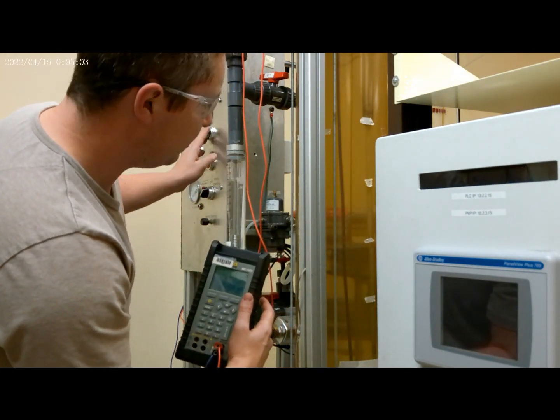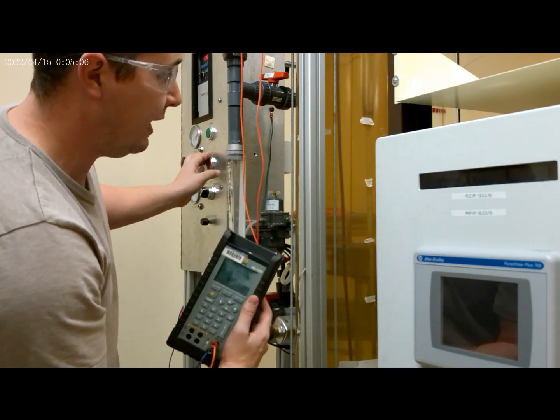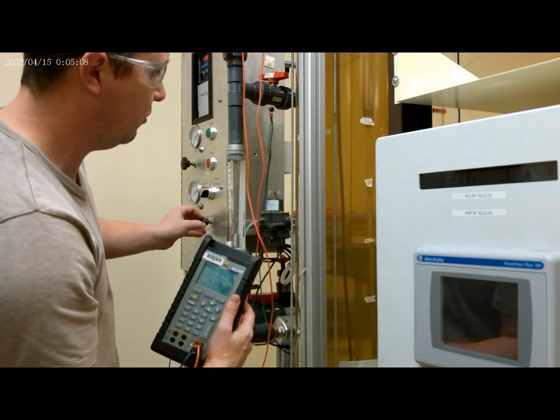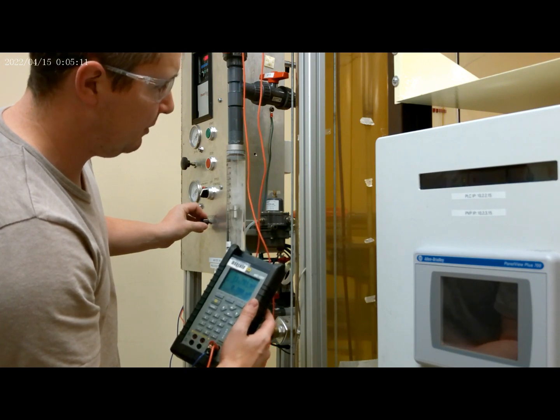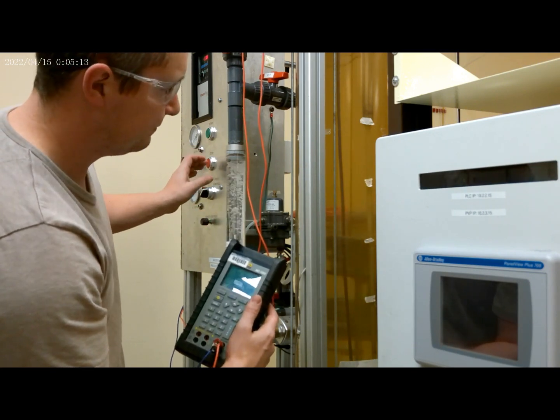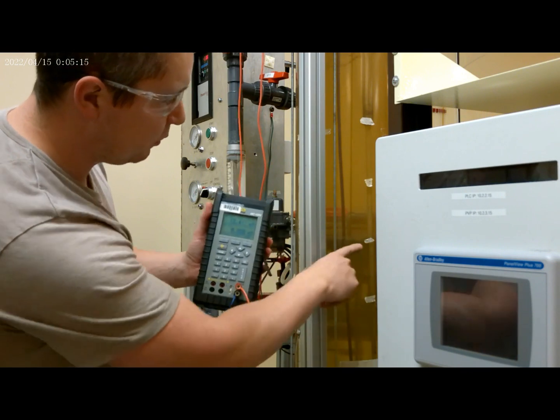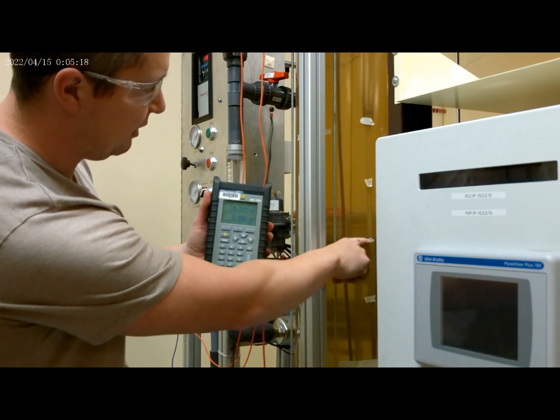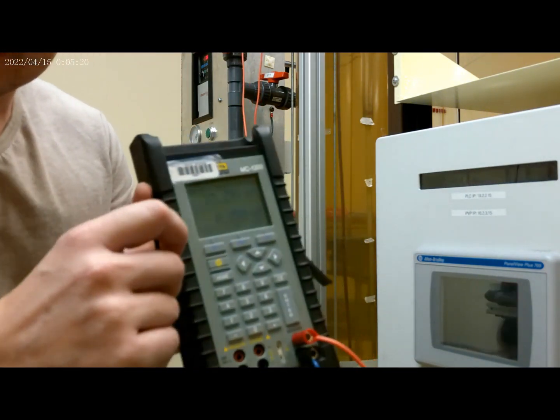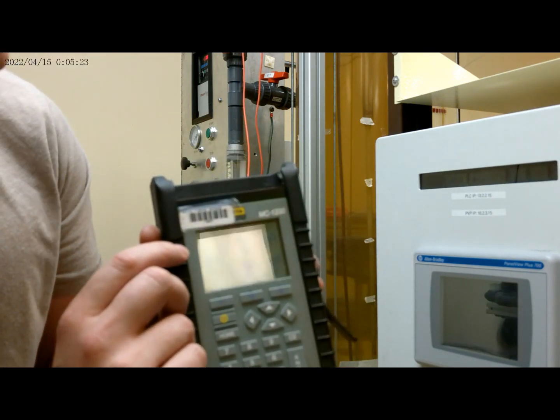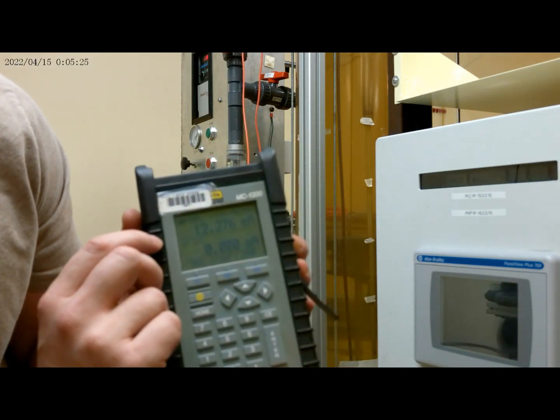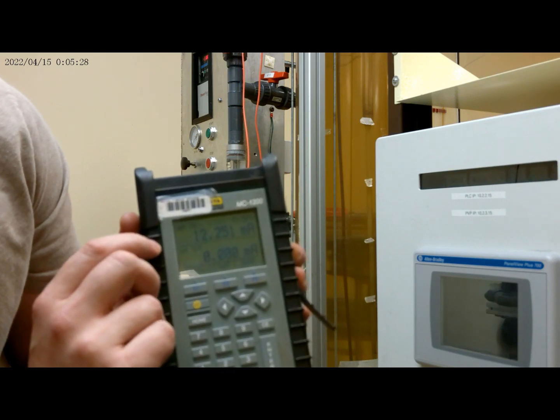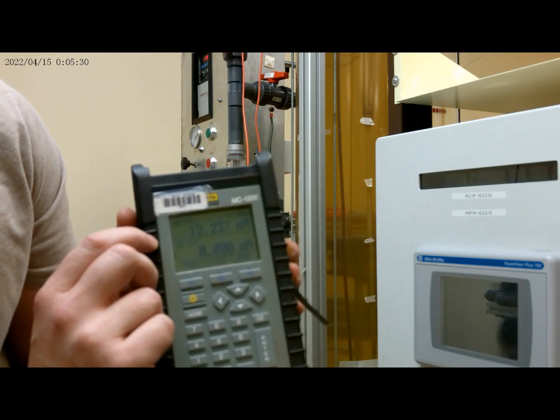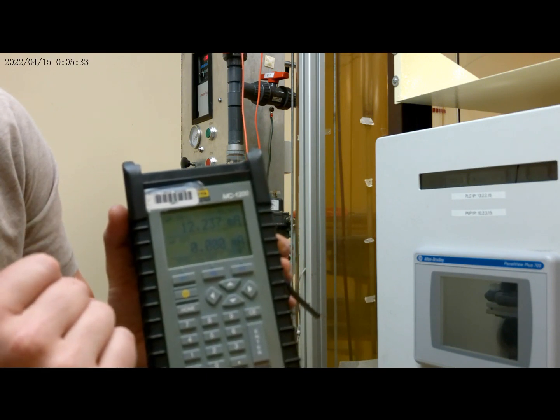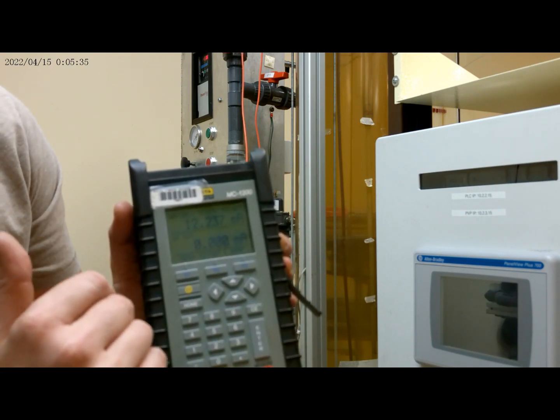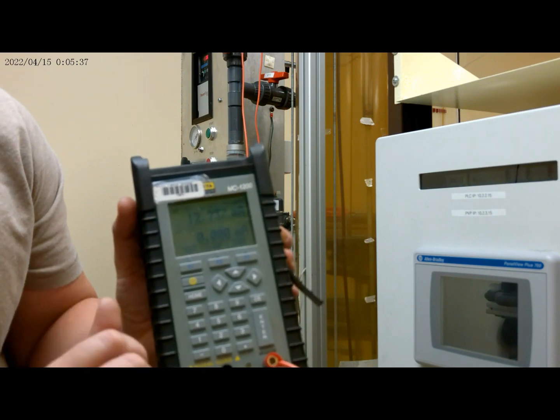That's not good for an accurate, fast reading of the probe, so we're going to go up a bit higher. Okay, we're very close to the 12 mark, a hair above at 12.3, and it's moving down. That's because some water splashed up on it, and as it drips off, the reading drops slightly. That's why it doesn't like splashing.